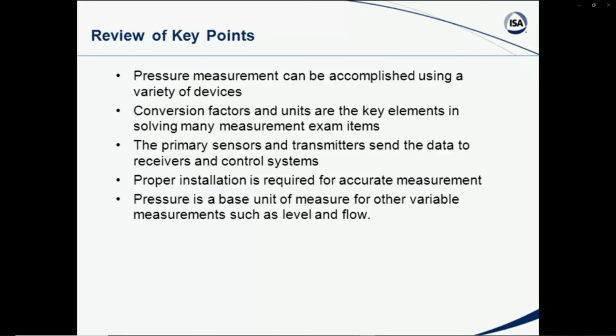But the purpose here is for the sensors and transmitters, in this case pressure, to get that data or intelligence back into the receivers and to the control systems. And one thing that I always mention to people, I think is very important, all instruments will work if they are applied properly, installed properly, and maintained properly. And I think that's a key thing that they check you on from a practical standpoint: do you know how to physically install instruments, valves, things of this nature? So you need to be aware of those and up to date on those.